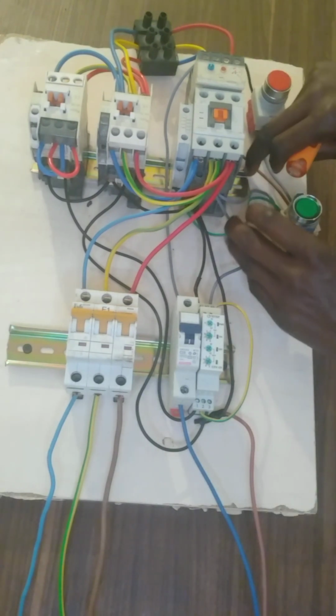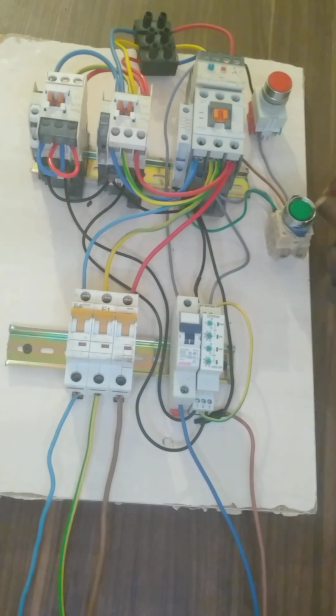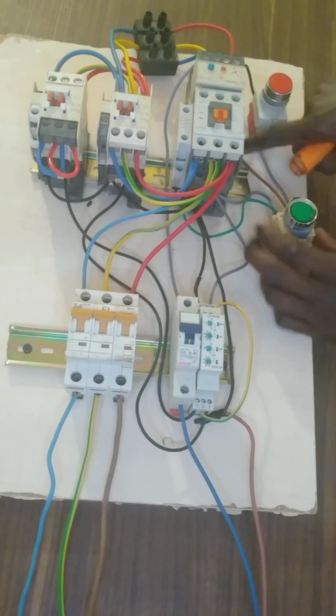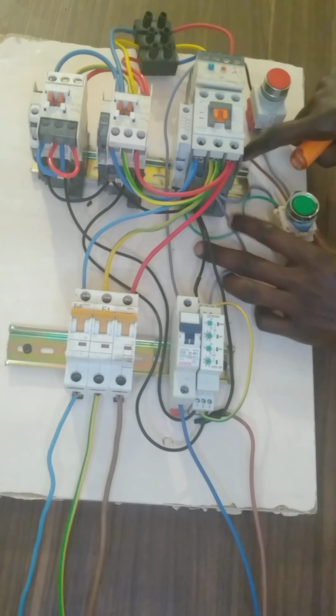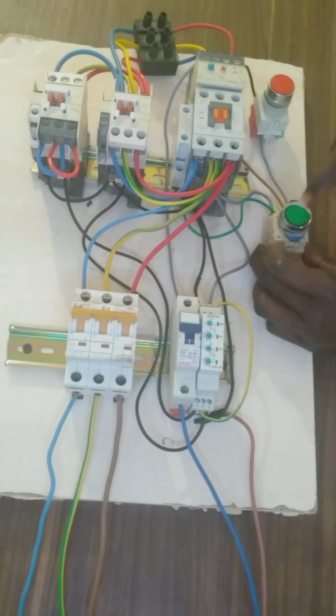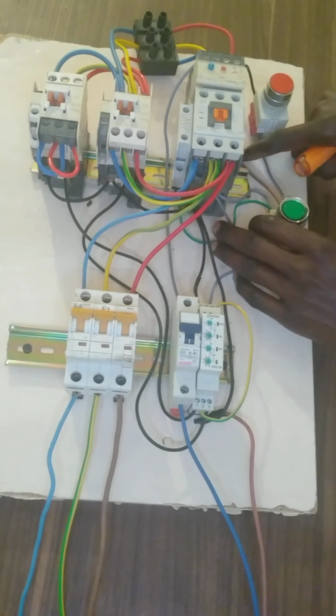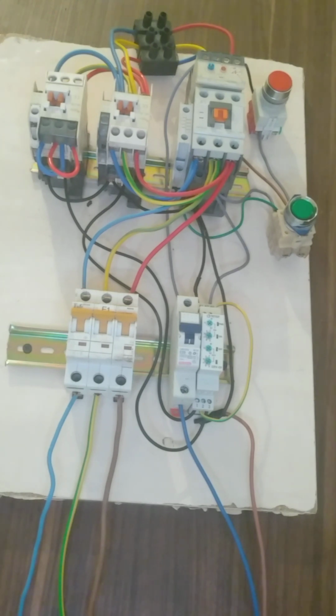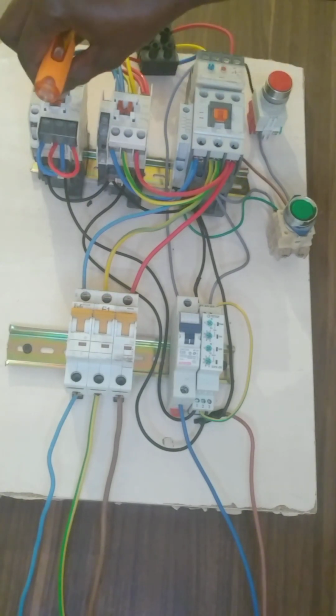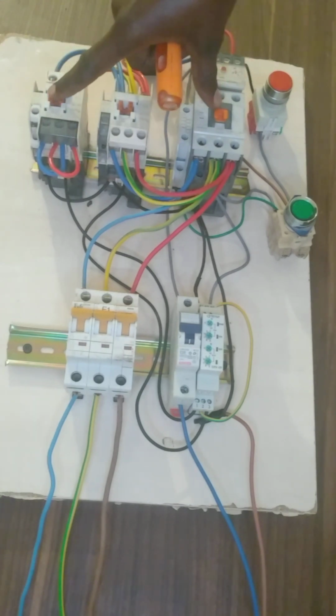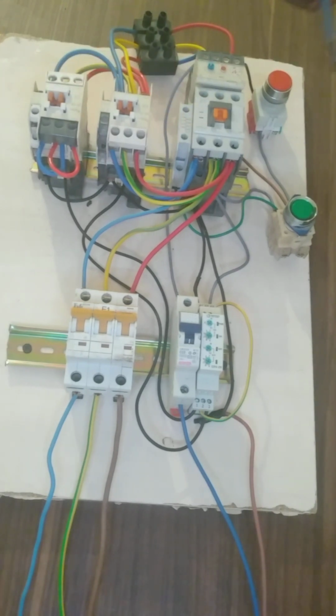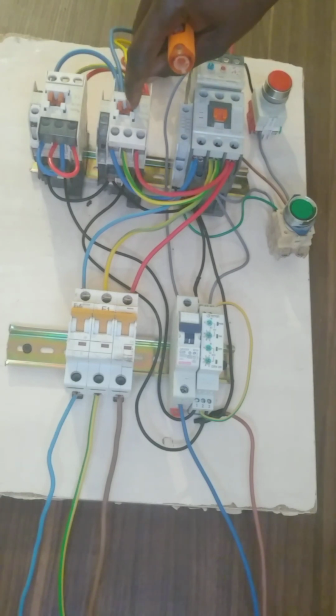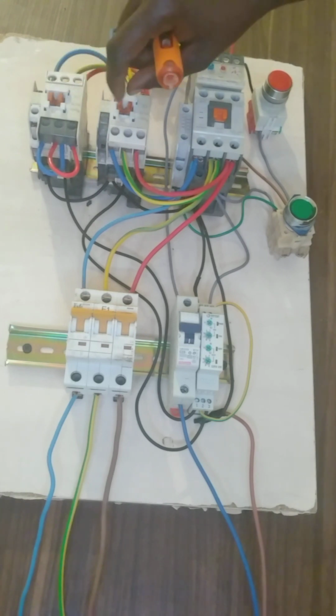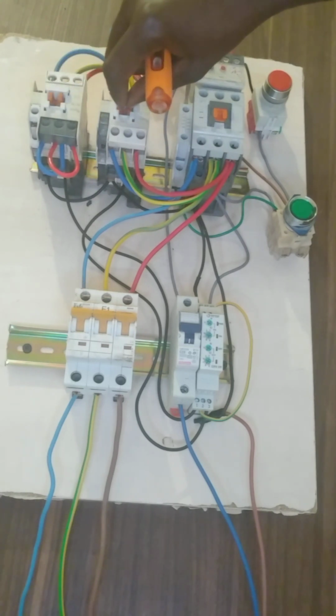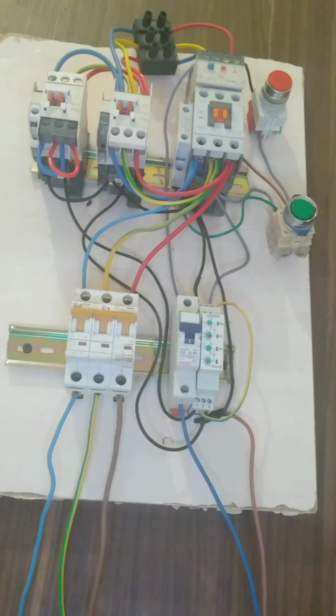Then I make the latching here from the normally open contact. In our videos we talked about this normally open contact and how to do the latching. So now if I press here, the main contactor and the star contactor start at the same time. Then after a few seconds, it changes from star to delta. It stops the star contactor and connects the delta contactor. So now I am going to connect the source.